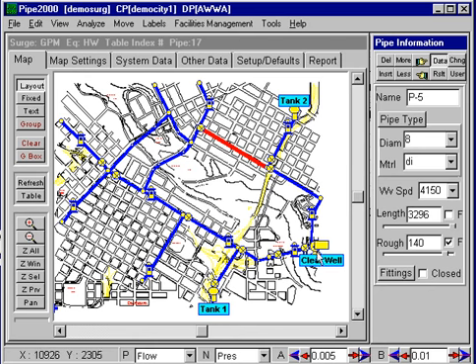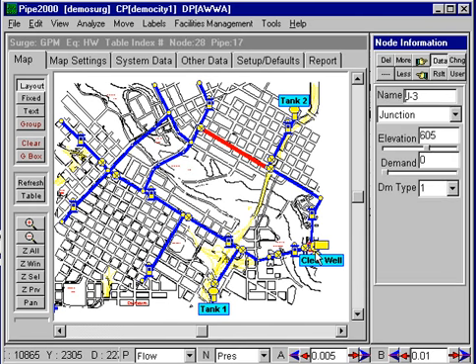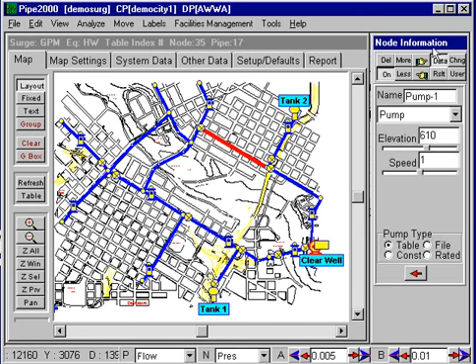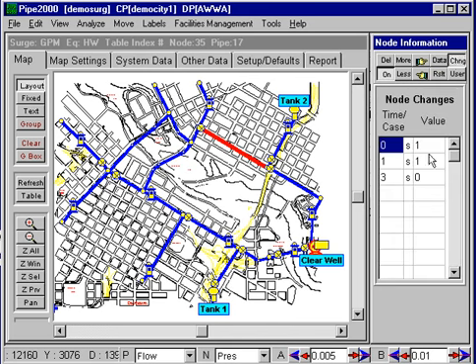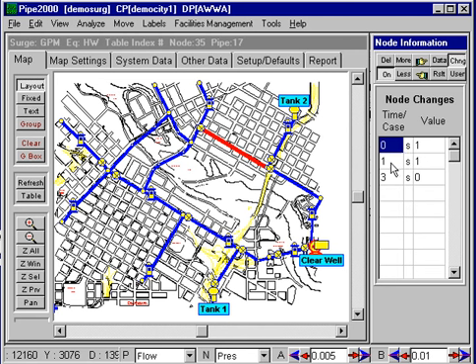To do that we select the pump and look at the change data, which is where we describe the shutdown of the pump. We first clear out all the changes from the regular simulation and then add the changes that describe the transient. In this case the pump speed ratio — the ratio of pump speed to rated speed — is one at time zero, so the pump is running at full speed. We let it run at full speed for a second. At time one it's still at full speed, but at time three it's ramped down to zero. So it's a two-second pump shutdown, and that describes the transient.